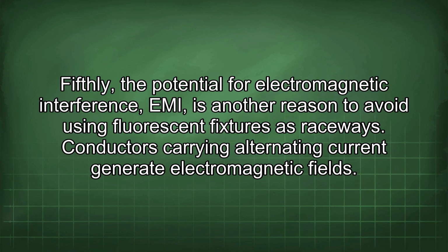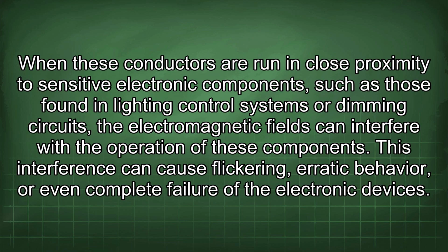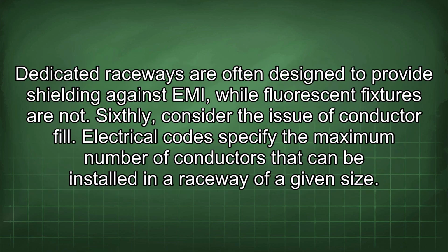Fifthly, the potential for electromagnetic interference, EMI, is another reason to avoid using fluorescent fixtures as raceways. Conductors carrying alternating current generate electromagnetic fields. When these conductors are run in close proximity to sensitive electronic components, such as those found in lighting control systems or dimming circuits, the electromagnetic fields can interfere with the operation of these components. This interference can cause flickering, erratic behavior, or even complete failure of the electronic devices. Dedicated raceways are often designed to provide shielding against EMI, while fluorescent fixtures are not.